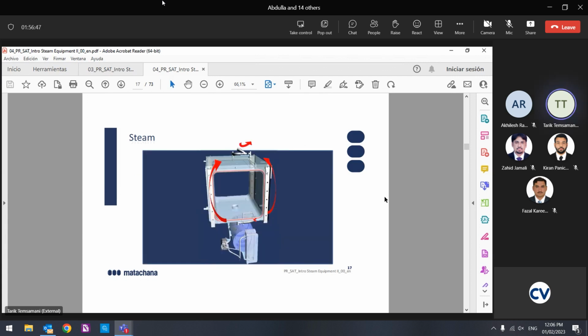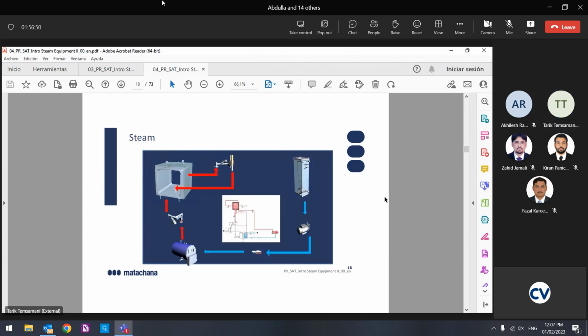This is the jacket. I showed you what we use the jacket for. Then the tank. Which water do we have here? Our water. Pump, other tanks. With the pump, we fill the steam generator. We have the pressure. We open the pneumatic valve. We fill the jacket, and then from the jacket to the chamber. It's easy? Simple, no? And only here we have a security valve for the jacket in case the pressure is too much, and a pneumatic valve. We open this pneumatic valve, and automatically, with the pressure, steam comes from the jacket to the chamber.